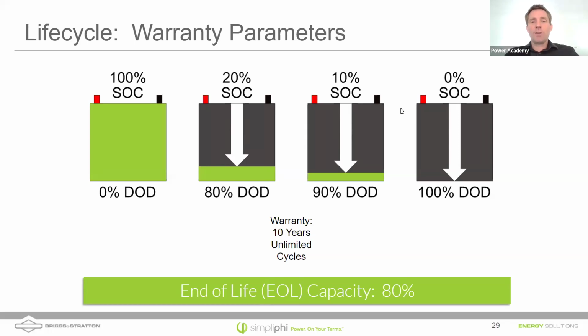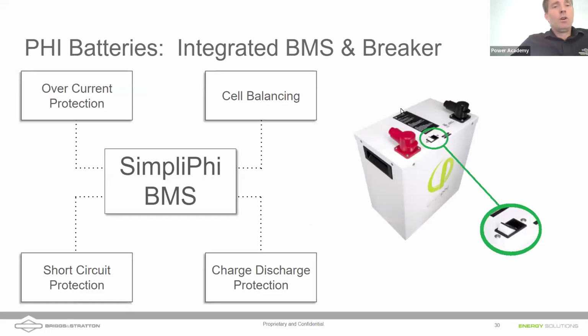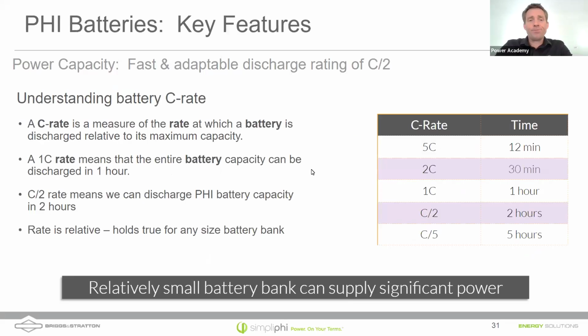All of our batteries have integrated breakers on them. The AmpliPHI and SimpliPHI batteries, the 5 batteries, all have 100 amp breakers now. All of the batteries have an internal computer called a battery management system, programmed for cell balancing, charge and discharge protection, short circuit current protection, and overcurrent protection.